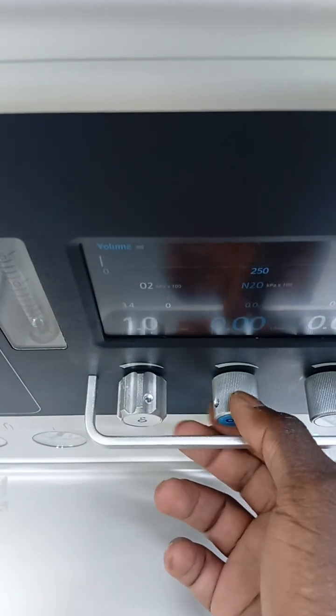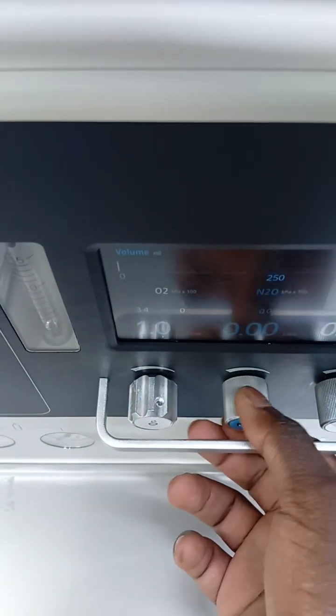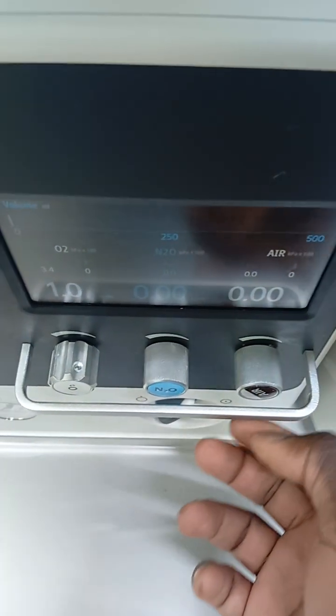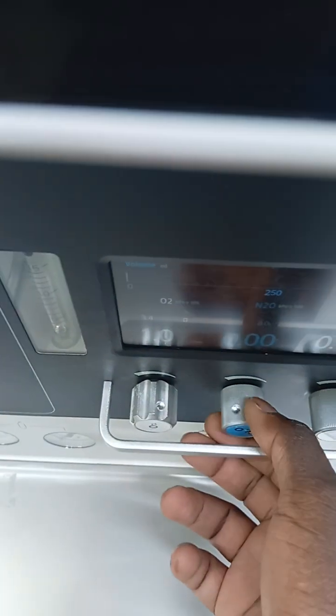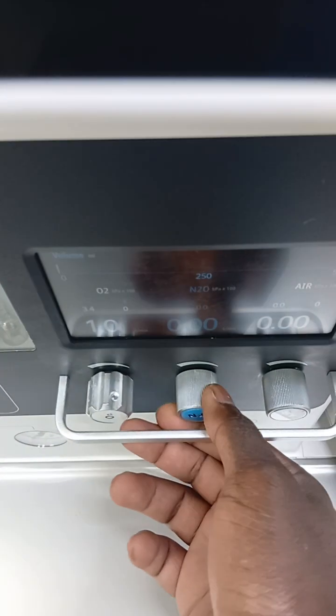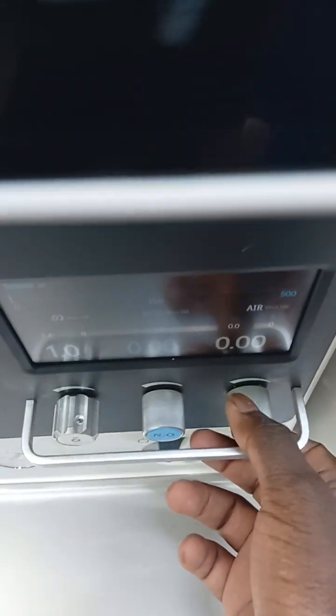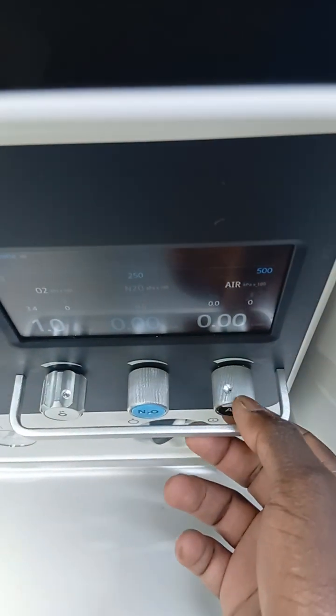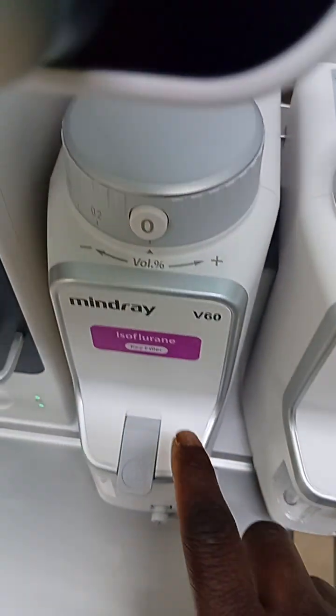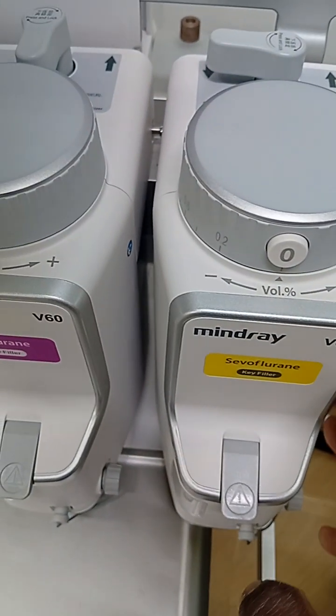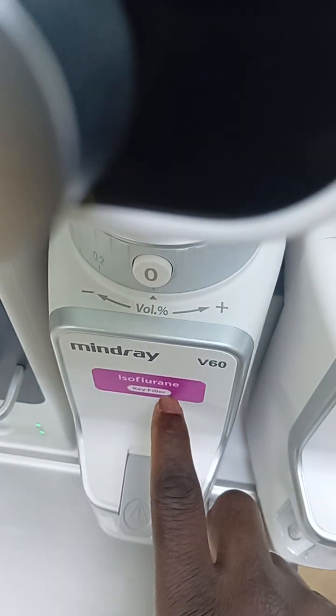There are some contraindications for nitrous oxide, for example, intestinal obstruction, because nitrous likes to displace other gases. In such instances, you have to use air to dilute your oxygen. So next to those knobs are, of course, the vaporizers. We have this purple vaporizer, and we have this yellow vaporizer, which we call sevoflurane and isoflurane.